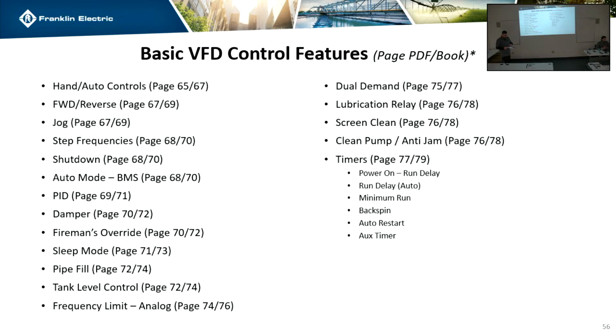The manual has a chart of just your kind of binary on-off as to if the inputs are off or on, what the drive is going to see. Let's see. The HOA mode source, set 60, that's the one I was telling you about. By default, it's going to be set to the keypad. But if you have an HOA, we're going to set it to digital input. So that's set 60. If it says keypad, everything on the hand and auto buttons is going to work. Once you go to digital input, it's going to be looking for digital inputs that are set to hand and auto. We use MI7 and MI8 for that.